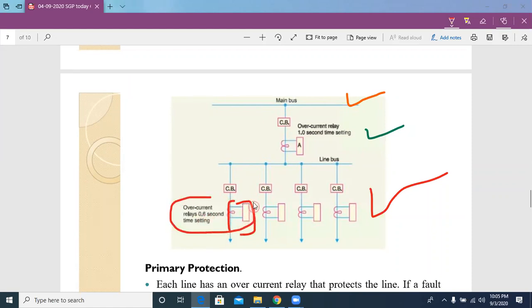The nature of a relay is like this: it activates immediately when the fault happens, and to operate it takes 0.6 seconds. The type of relay, meaning the activating quantity, is overcurrent. It is an overcurrent relay, which means when the current value exceeds the relay preset value. Let's assume the relay preset value is 1 kiloampere.